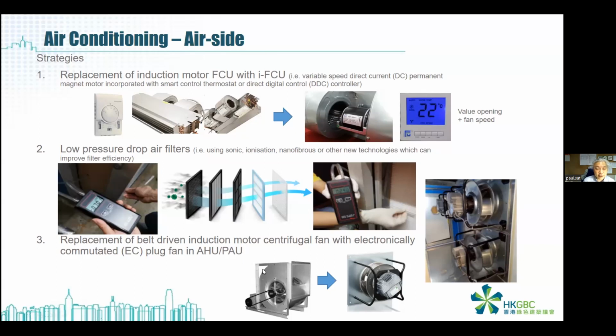Another very common measure in recent years in Hong Kong is to convert the belt drive centrifugal fan, for both air handling units and primary air units, into what we call the electronically commutated EC plug fan. This fan does not require a belt. It's direct drive. That is the first point.